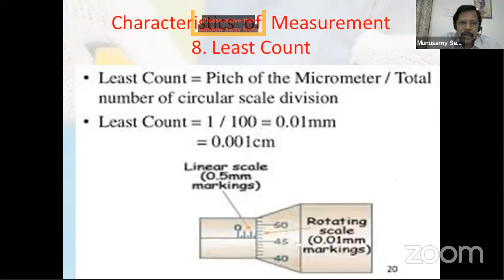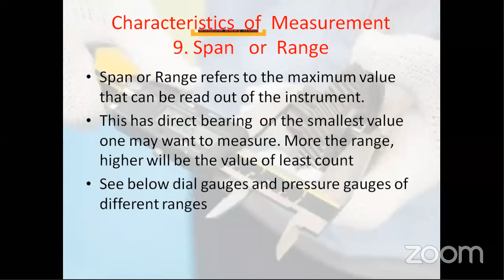The next one to be seen is the span or the range. The span or the range refers to the maximum value that can be read out of the instrument. Sometimes you require to measure a 10 millimeter deflection. There you cannot use a 2 mm dial gauge to measure a 10 mm deflection. So you will go for a 50 mm dial gauge, which means you should choose a dial gauge which has a higher span or higher range. That's what we call the range or the span of the instrument. Obviously, when you go for a very high range, the smallest value you get will be only slightly more than what is normally available in a smaller range.